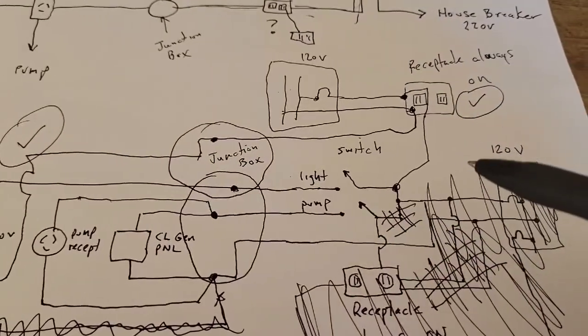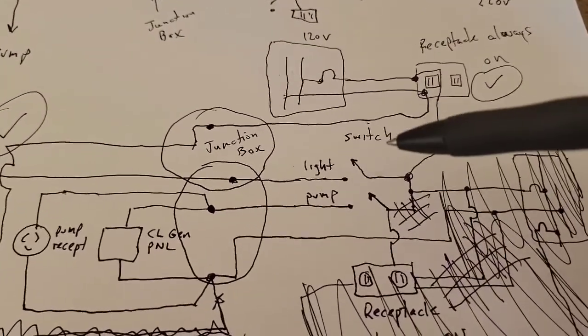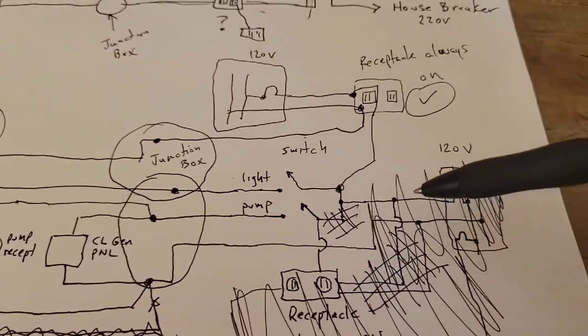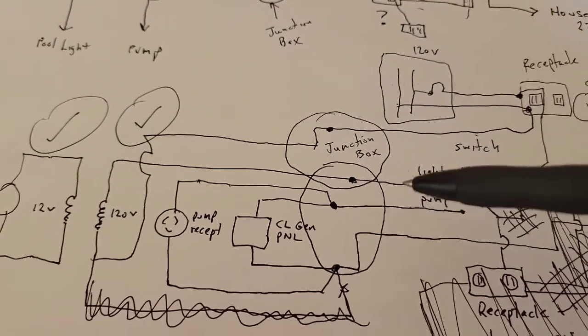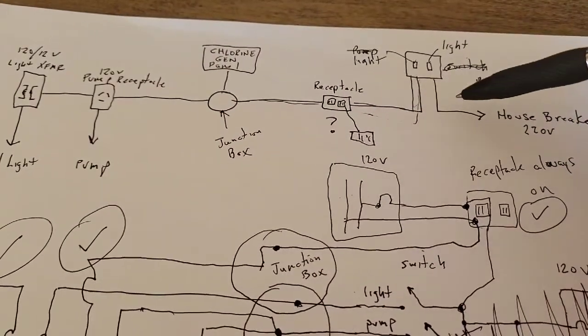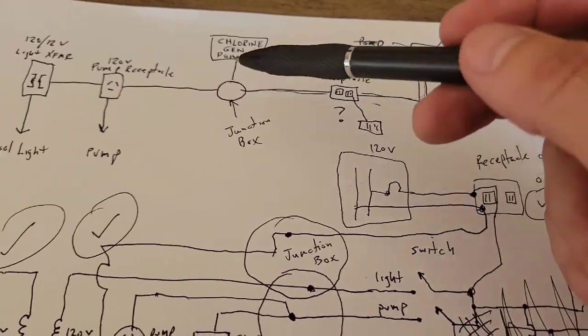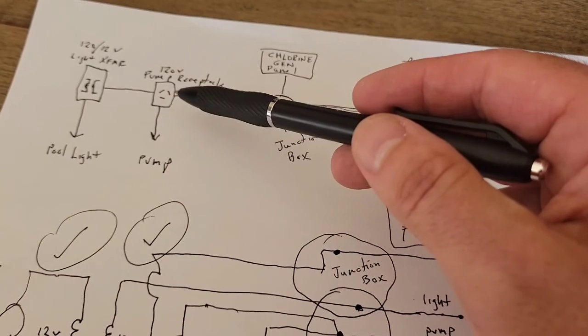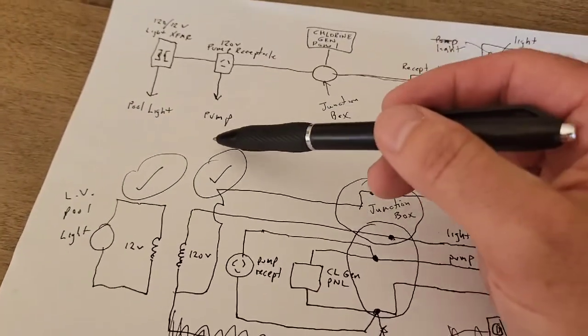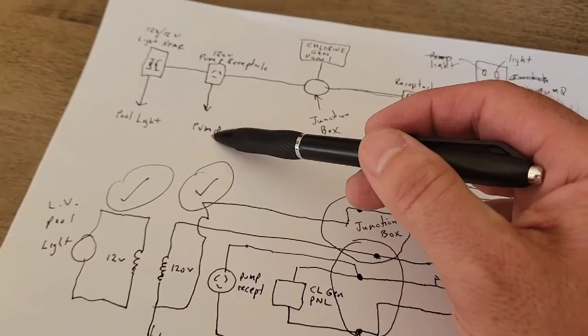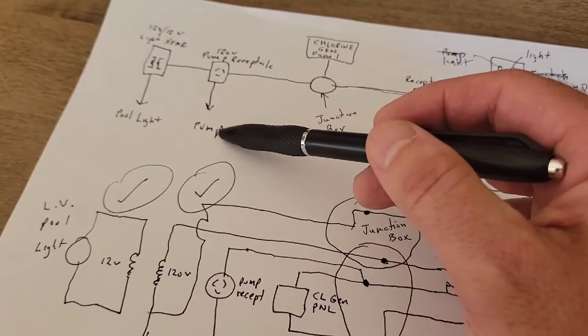So this was all messed up. Some of my original assumptions were wrong, but that's essentially the idea. I had no idea the light was fed directly by this receptacle until I started digging around the light switch panel. So I rang out everything from the junction box panel to the pool light, and then when we figured out the breaker had tripped and verified this switch was okay to the pump, the pump receptacle did have 220 volts. So now we have to put the pump motor back, so the original owner was correct. It was a 220 volt operating pump off of a separately fed yoked breaker.